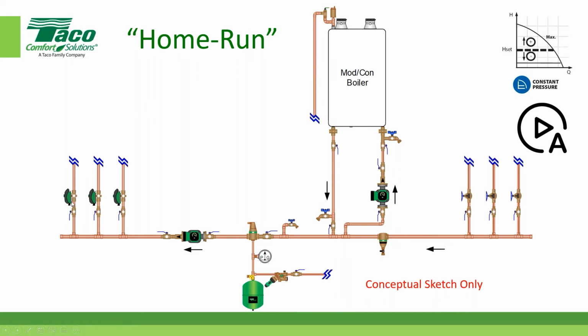I touched on this earlier in the sessions that we did. One of these zones is going to be the worst case, and that sets the precedent for what this circulator would need to be, so it would be appropriately sized. So in a home run application, we want constant pressure for this circulator, but we don't want it for that one. That's why you'll see the appropriate check mark by the circulator at hand. Why does it make sense? If I want to be able to overcome the resistance under a design condition of the worst of these three zones, I'm going to have to maintain that, because of the likelihood of that zone, the worst case, calling all by itself under a design load condition. So that's why we do it.